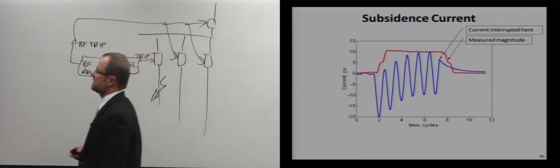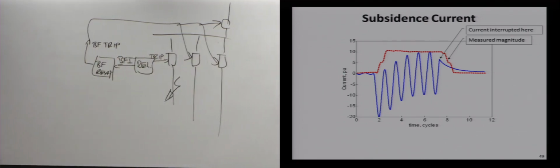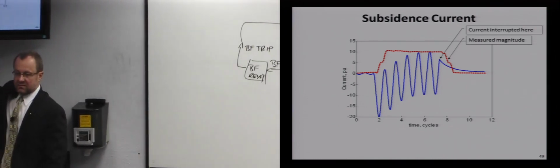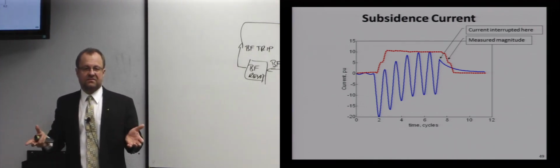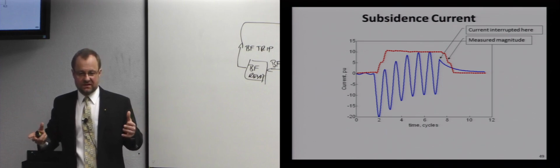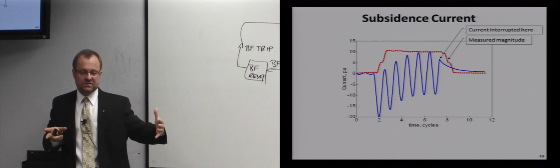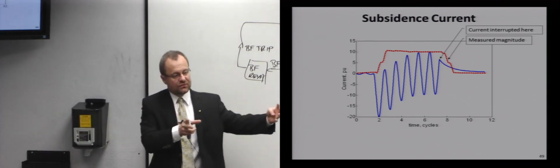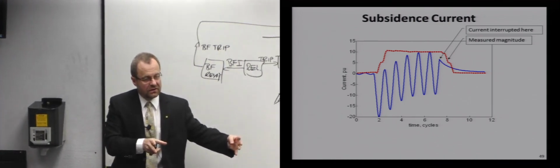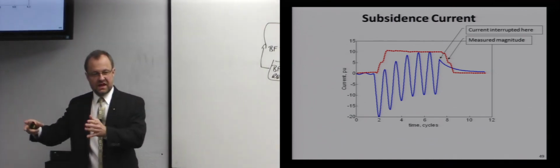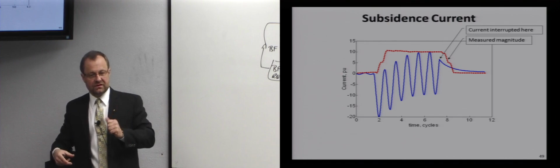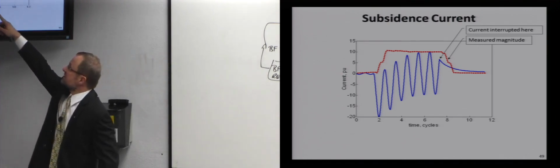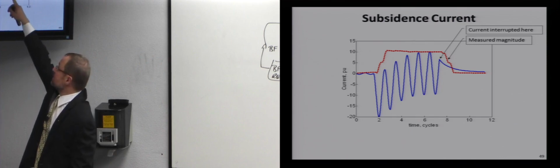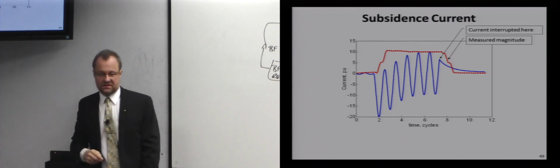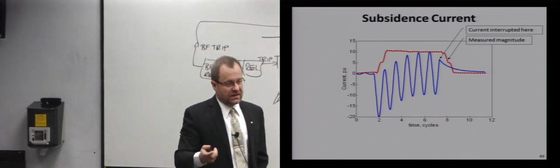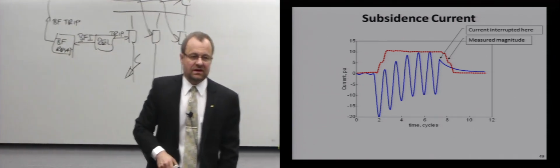At the same time, it takes some time to make a transition from pre-fault to fault, because any FIR filter is an averager, right? It does a weighted average of the samples within the window. So the window needs to fully slide from the pre-fault to fault to have the output making a transition from the pre-fault to fault. So the same dynamics that we have on the rising of that current will happen on the reset of that current, right? So it will take maybe a cycle to realize that that current is gone.